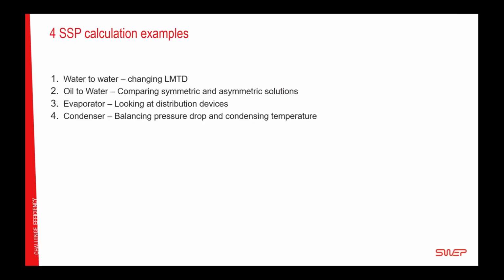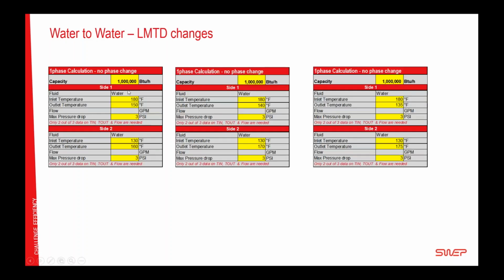So that was how to find out the data we need, and now let's look into SSP. I will say like this. What we will look at here are four cases: water to water, where we'll be changing the logarithmic mean temperature difference and see what happens; an oil to water, comparing symmetric and asymmetric solutions; an evaporator at different distribution devices; and a condenser, balancing the pressure drop on the water side and the condensing temperature. So let's start with the water to water changing LMTD.